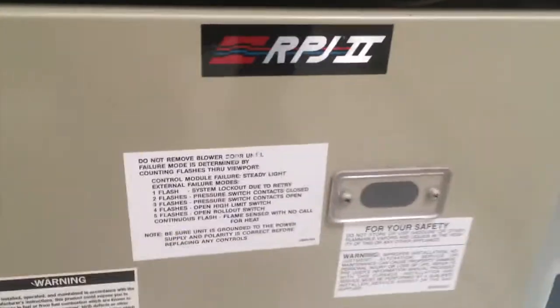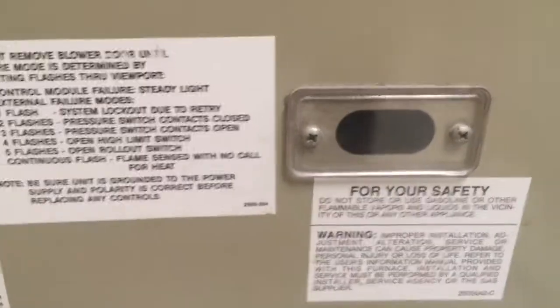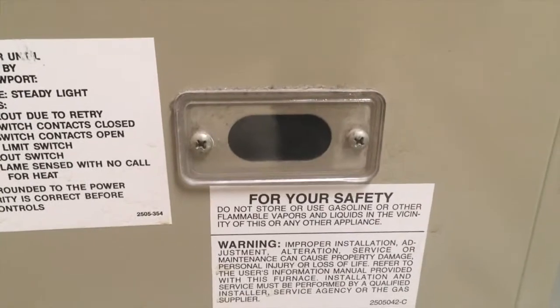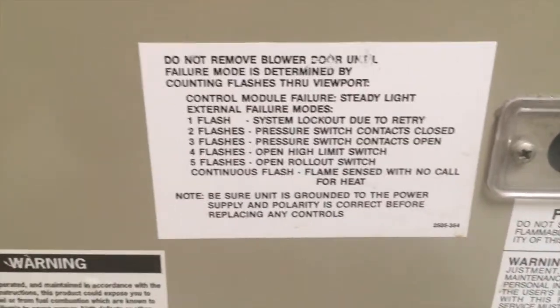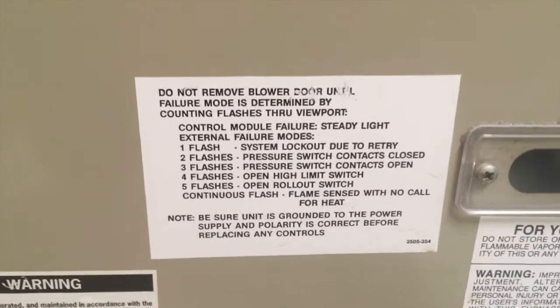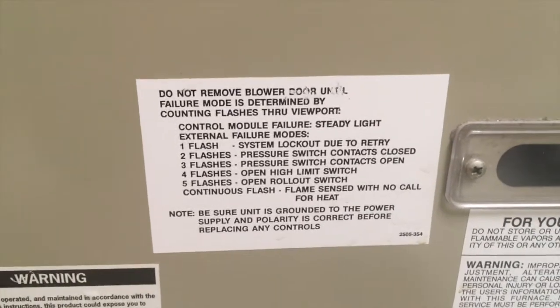After it shuts itself off, basically, I get 6 flashes that I see through this window. Unfortunately, that doesn't show up on the little legend that's here on the front of the furnace. So I did some digging, and it turns out that 6 flashes indicates a shorted flame sensor probe, per the manufacturer. So we're going to clean the flame sensor on this furnace and see if that fixes the problem.